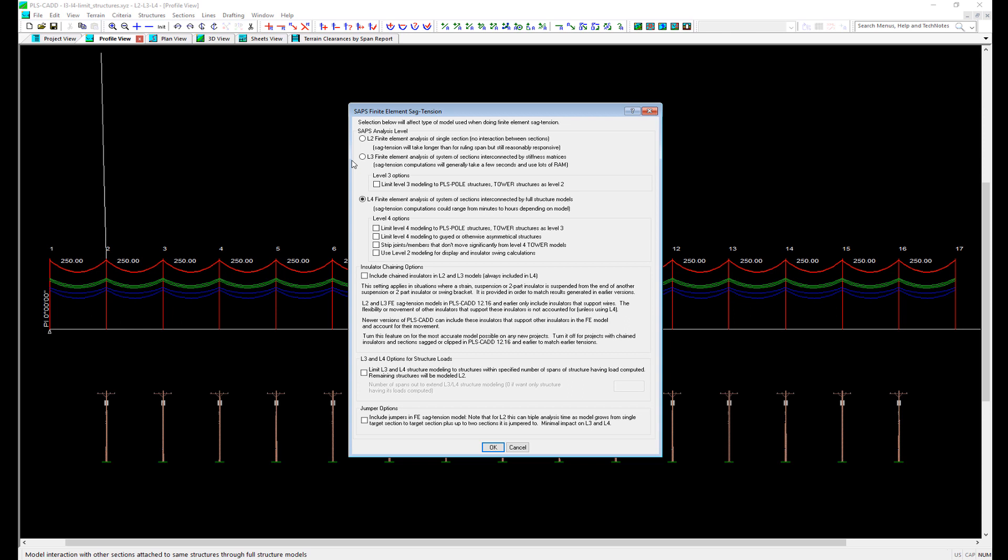By default, a PLSCAD project is assumed to be in SAP's Level 2. When a model is in SAP's Level 2, all structures are treated as being infinitely rigid when the sag tension analysis is performed. Structure deflection is not considered during the sag tension analysis with SAP's Level 2. Interaction between spans and insulator swing in both longitudinal and transverse movement is considered in SAP's Level 2 and can be considered very quickly.